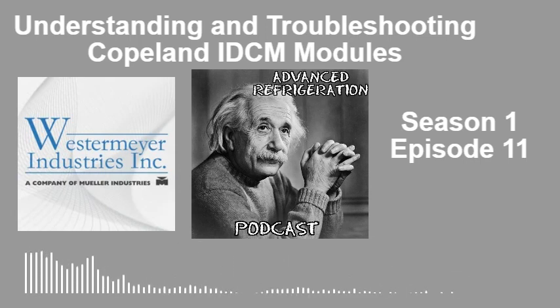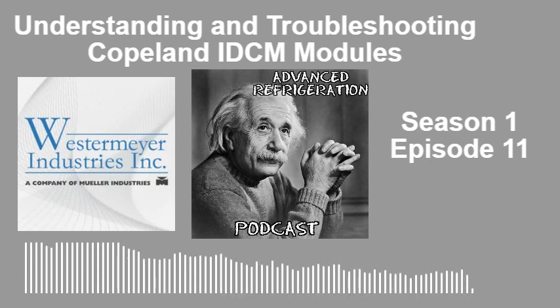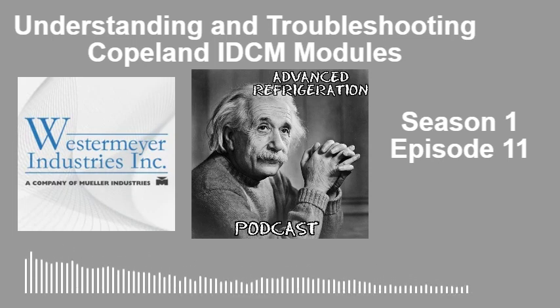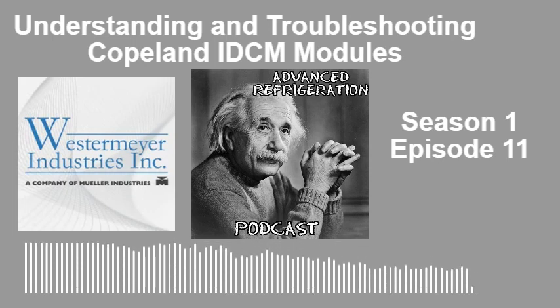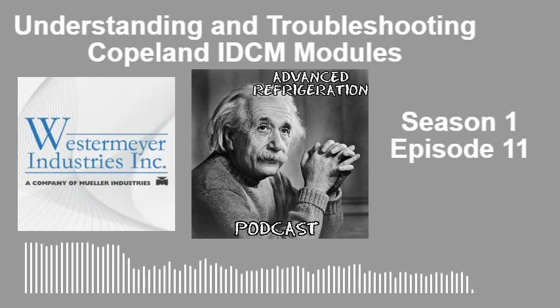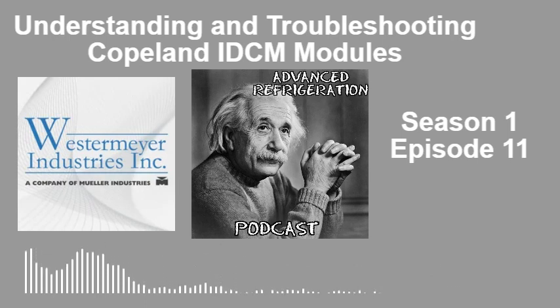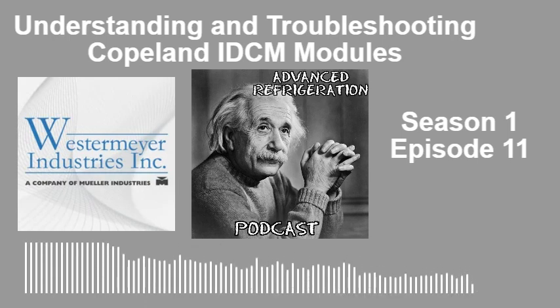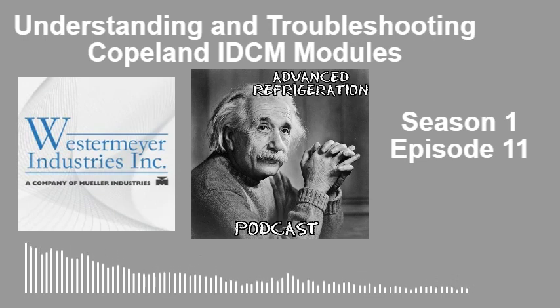Generally, it's set to 20 seconds. Really? Yeah, it's usually a 10% minimum with a 20-second cycle. That's generally what I see them set at, and that's generally what I put them at. So if it's a 4D, it's going to be a 50% minimum. And if it's a 3D, it's going to be a 10% minimum. And same with the scroll, it'll be 10%.